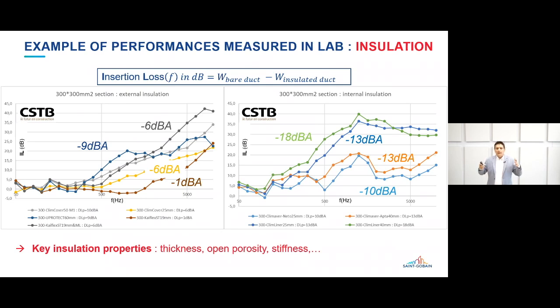So the key insulation properties to consider when you want to increase the insertion loss of your HVAC system are: thickness - the more thickness you have, the better the performance; open porosity - if the facing is open, it absorbs more noise and decreases the noise perceived outside; and the stiffness of the product, because depending on the system it can add more, as Elodie mentioned before. That's all on insulation for insertion loss. Now Elodie will present the linear attenuation.